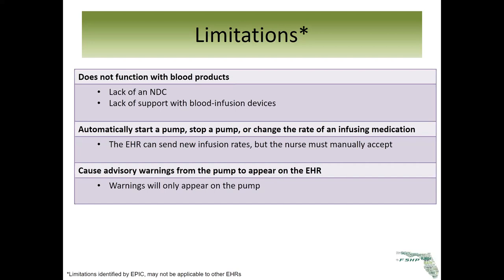Secondly, and I think this is probably the most important thing I need to stress, is that interoperability does not allow for the automatic start, stop, or changing of infusion. I'm going to say that again because it's very important: interoperability does not allow for the automatic start, stop, or change of an infusion. The EHR can send the new data to the pump, but the nurse or other provider must manually accept the new orders before the pump will change the rate of the infusion.